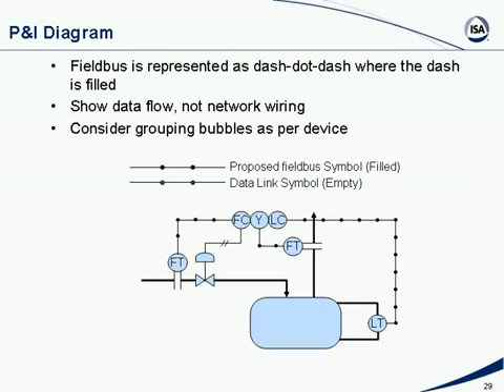An essential document for any control system is the P&I diagram. The most common question is, how do I draw Fieldbus? What does Fieldbus look like on a P&I diagram? Last time I checked, ISA had not really changed their standard, but what we're seeing in the market is that the proposed symbol for Fieldbus is a filled dot, whereas the internal DCS data link symbol is an empty circle. It doesn't look empty on the screen, but believe me, it is. That's how you differentiate between a DCS data link signal and a Fieldbus data link signal: the Fieldbus signal is filled.